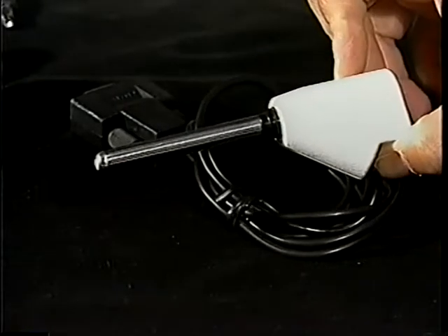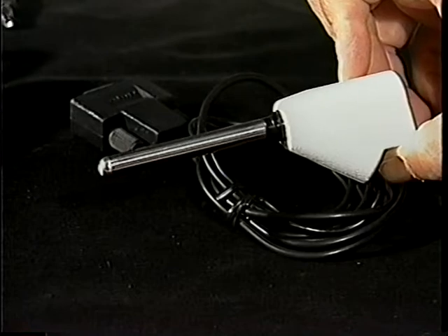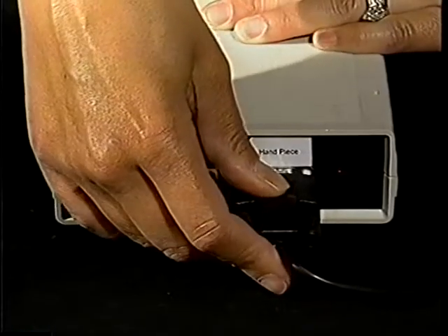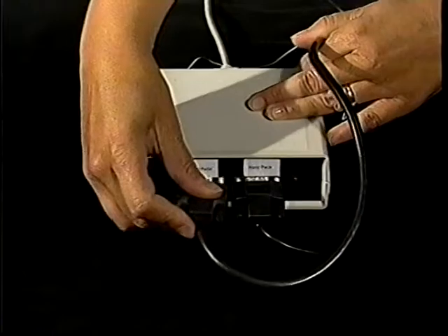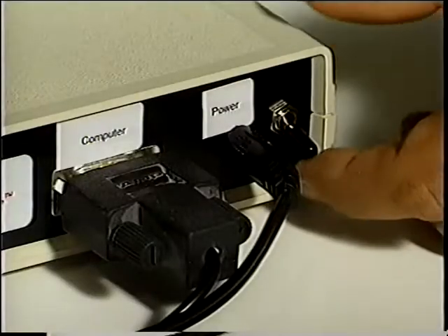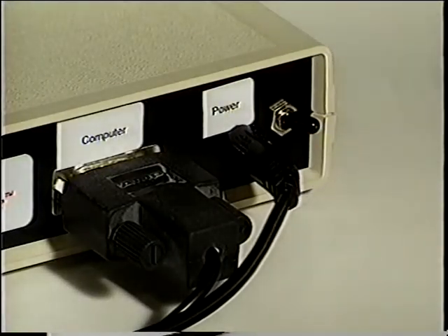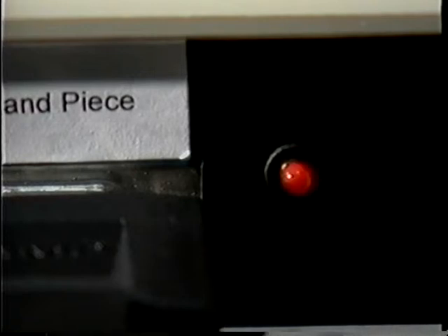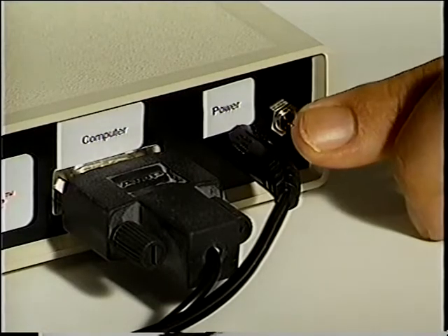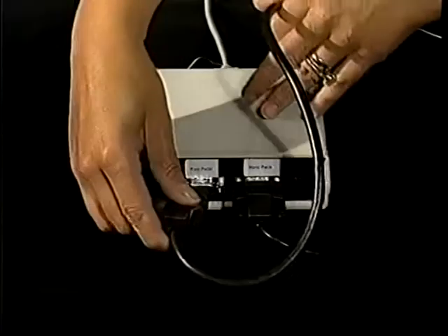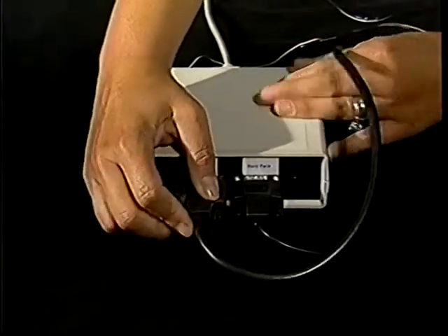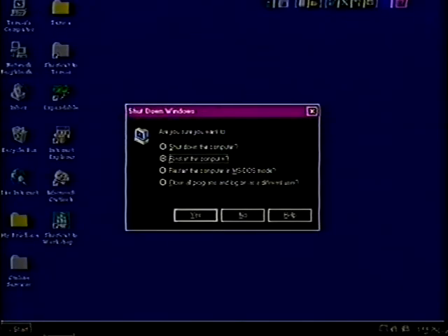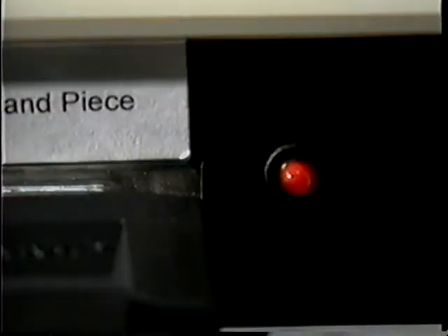The next step is to connect the encoder handpiece to the interface serial port marked Handpiece. And finally, connect the foot pedal in the same way. Flip the on-off switch upward. The red light in the front of the interface unit will come on to show you that the Probe One is powered up. The red light will stay on until you turn the switch to the off position. Now that your Probe One hardware is fully connected and powered up, it's time to reboot your computer. The Probe One should be left on as the computer is starting back up.